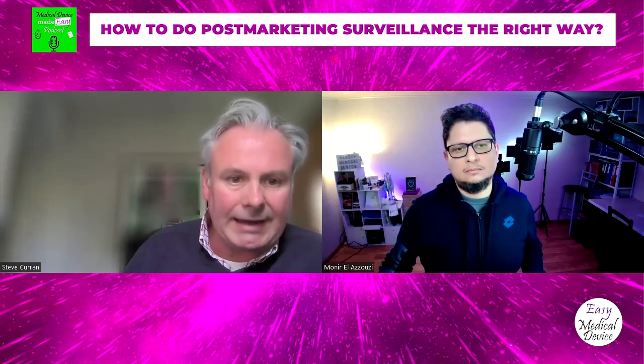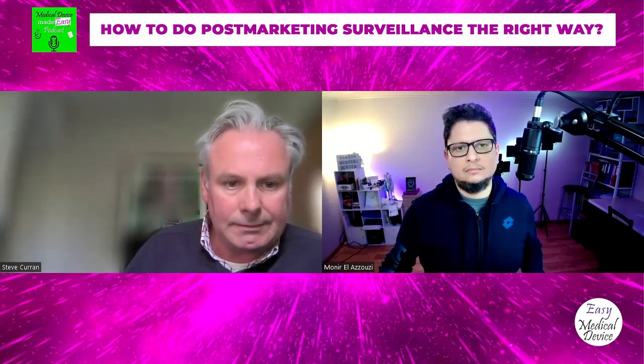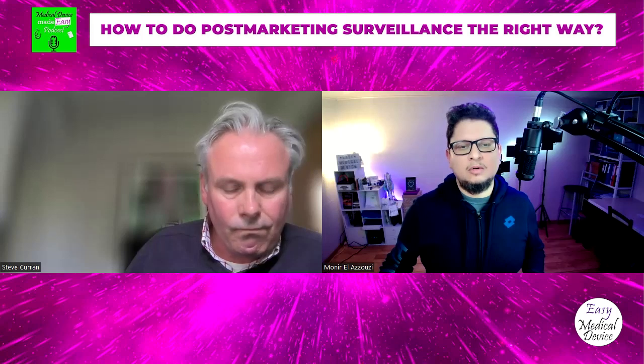When all of this comes out, like I said before, you've got to go back and, as a team, review your risk assessment, and then it may lead to other actions being taken, like redesign of a device and other things. All of this needs to be documented. All of it needs to be justified with good rationale, and all of the documentation this falls into has to be updated. And again, for the higher risk devices, when the notified bodies come round to do the review, they'll need to see that it has been done annually, and that it's all fully documented and approved.